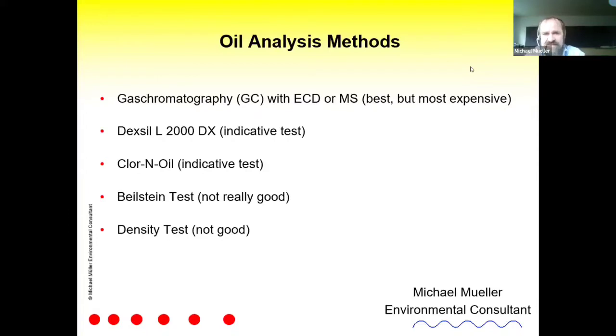For analysis, the best is always GC—gas chromatography with electron capture detector or with a mass spectrometer. It's the best, it takes the most time, and it's the most expensive one, of course. Then we have a so-called indicative test, such as the Dexsil L2000—meanwhile there's a new model—and the Clor-N-Oil. The difference is that the Dexsil L2000 is a device, more specific, while the Clor-N-Oil is more a test kit you can use on site.